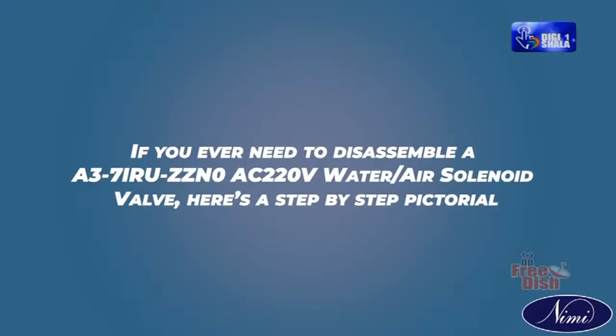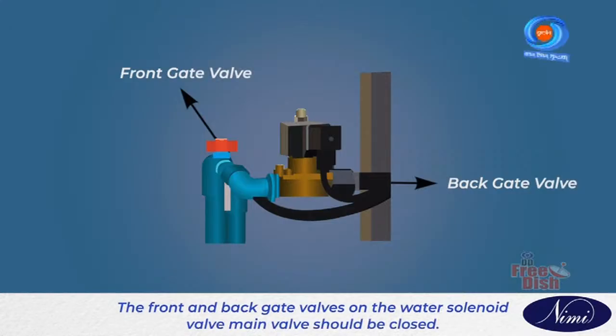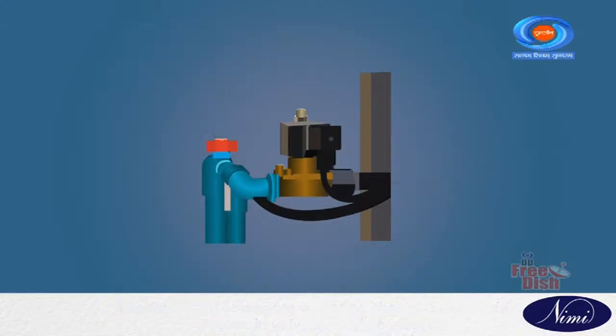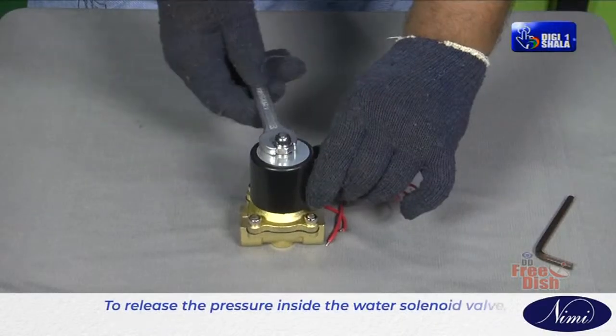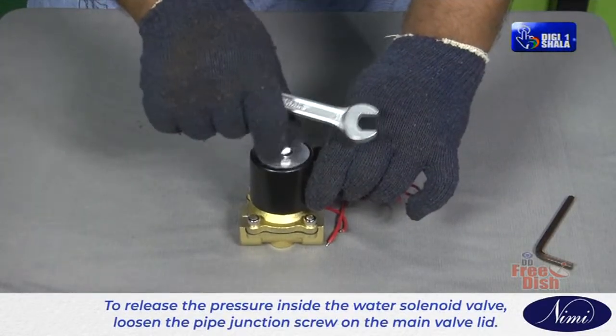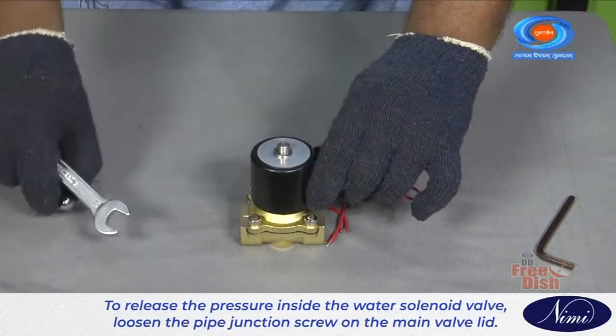Task 2. If you ever need to disassemble an A37 IRU ZZN0 AC 220 volt water or air solenoid valve, here is a step-by-step pictorial. Step 1. The front and back gate valves on the water solenoid valve's main valve should be closed. Step 2. To release the pressure inside the water solenoid valve, loosen the pipe junction screw on the main valve lid.